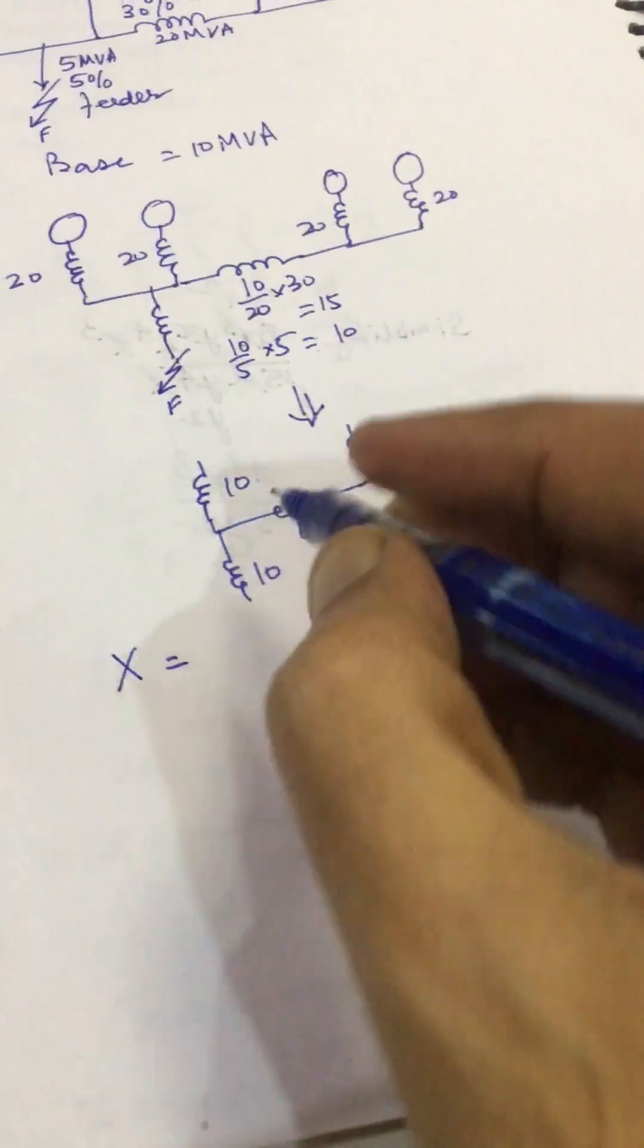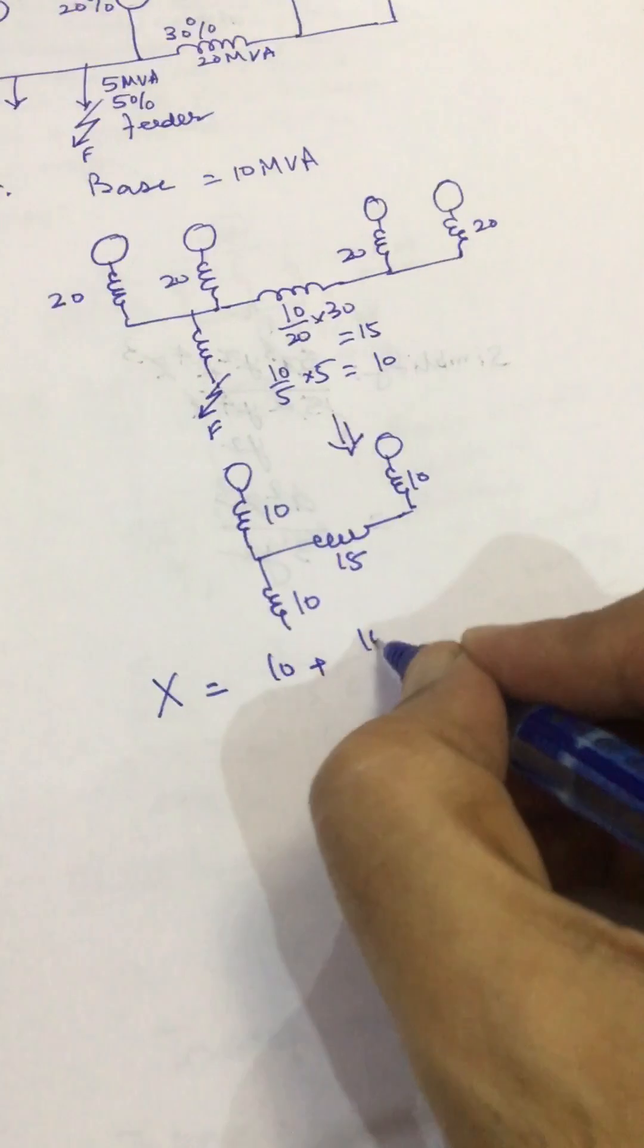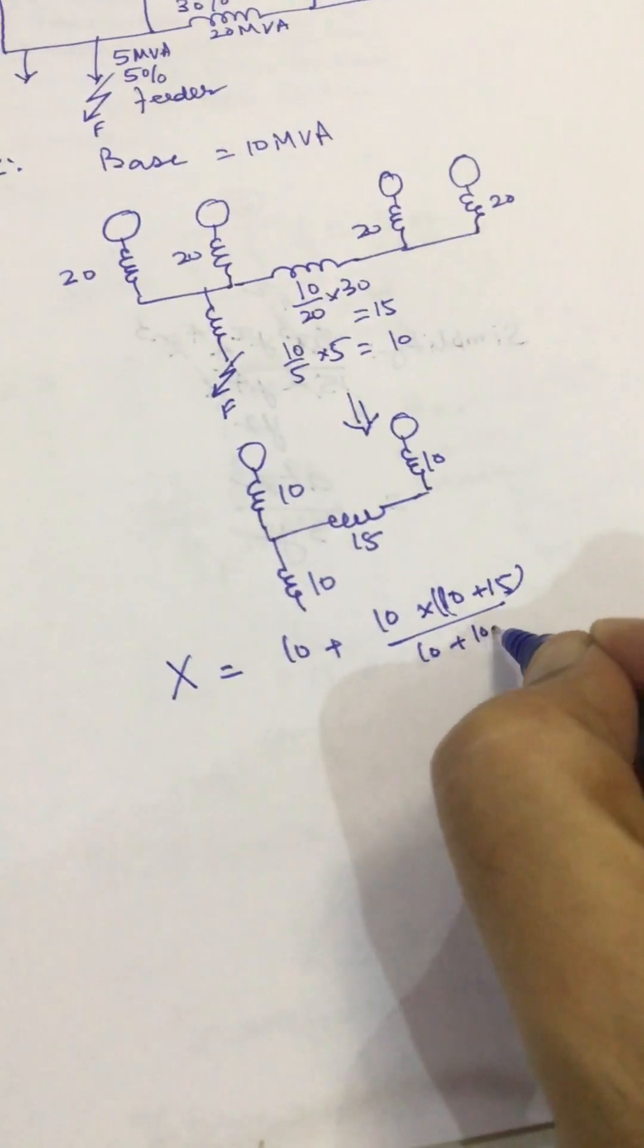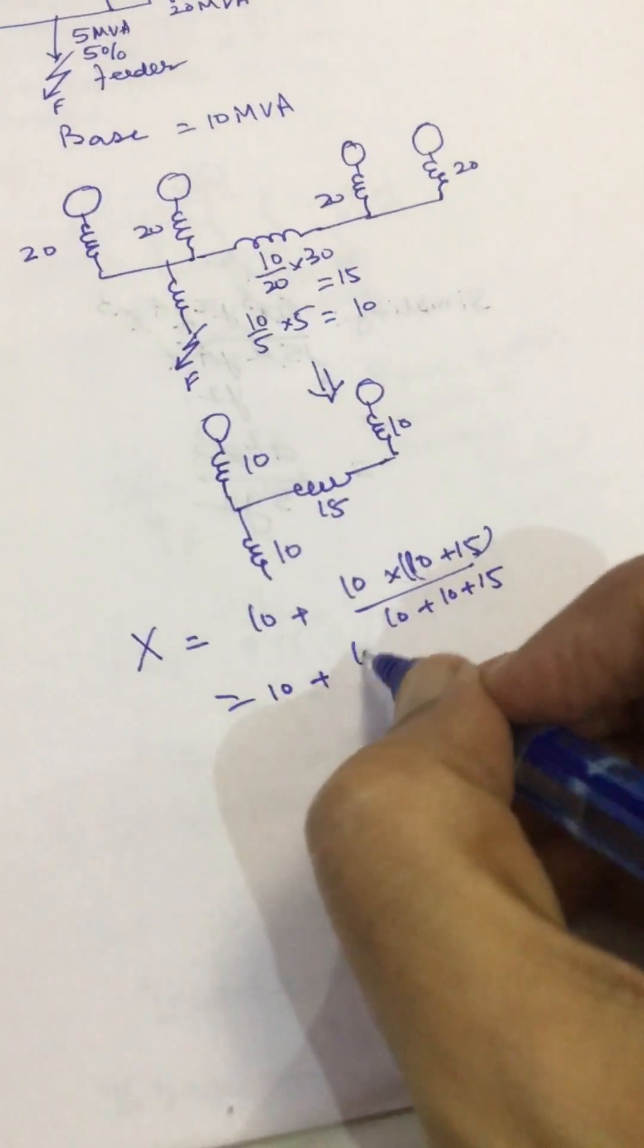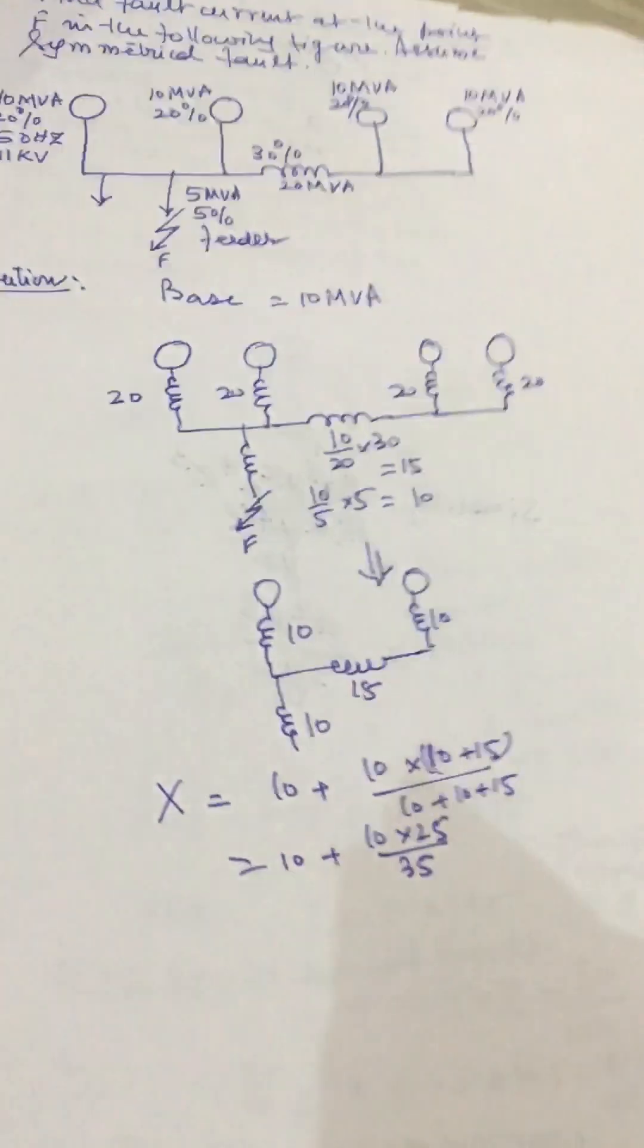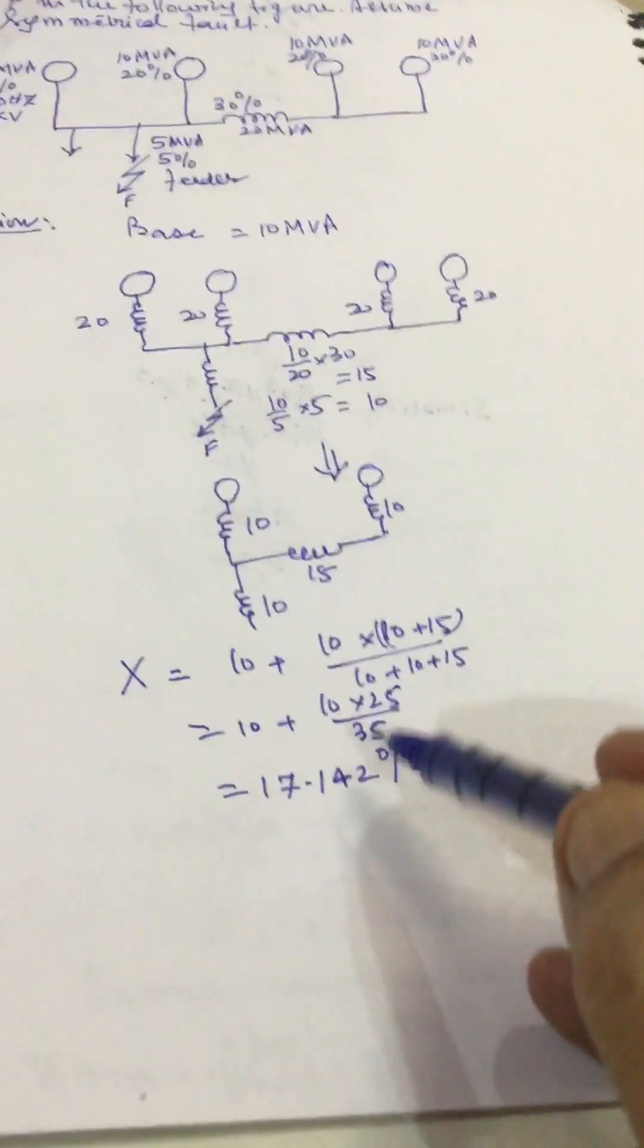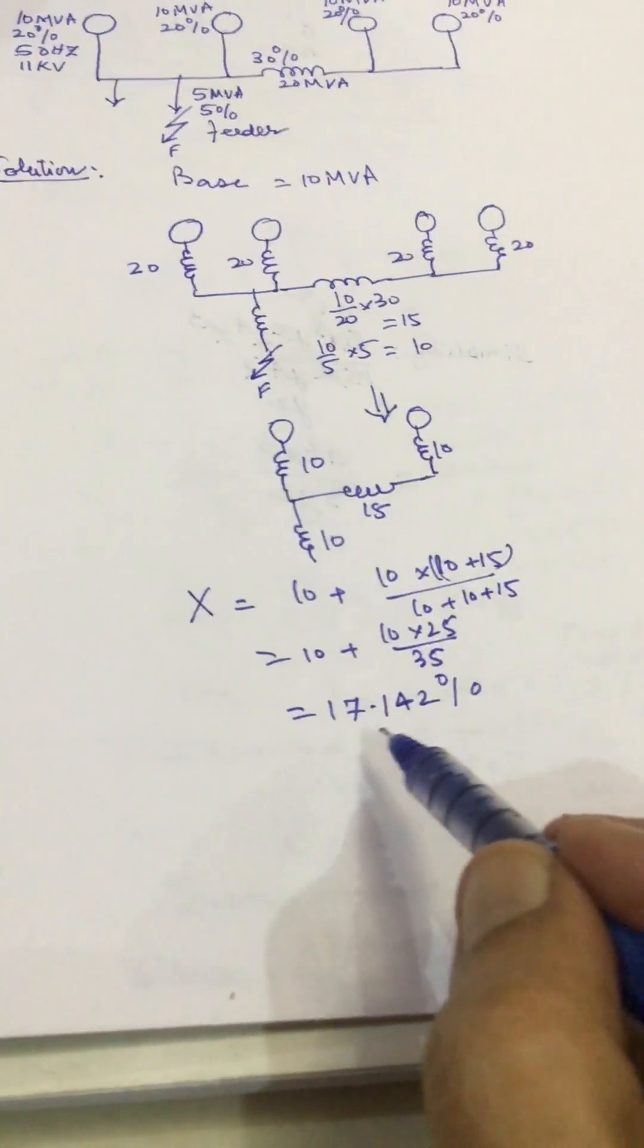Reactance up to fault from generating point up to fault: we have 10 plus 10 into 10 plus 15 divided by 10 plus 10 plus 15 equal to 10 plus 10 into 25 divided by 35, which equals 10 plus 250 divided by 35. If we simplify it then we get 17.142 percent. From generating point up to the fault the reactance is 17.142 percent.